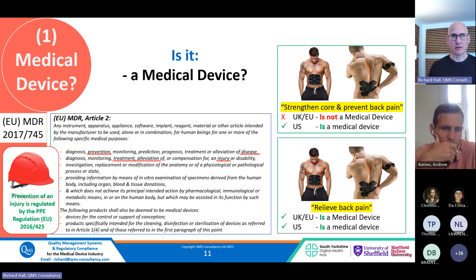The FDA make decisions and publish those decisions, whereas in Europe, we've got a process of writing down in a document, and the document then describes the legislation. So it's a slightly different process, but the Americans have decided that this product changes the physiology of the patient and therefore is a medical device, or falls under the medical device regulations, no matter how the device is described by the manufacturer. Most things other than this would be described under the PPE regulations 2016/425 for things like steel toe cap shoes and helmets to prevent injury. So there's usually a regulation, but it's not necessarily the medical device regulation.